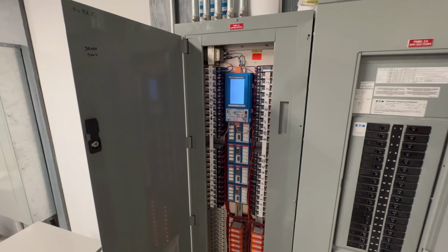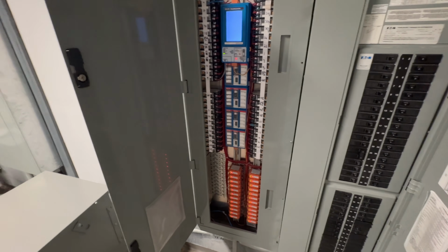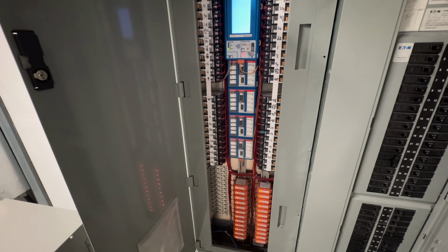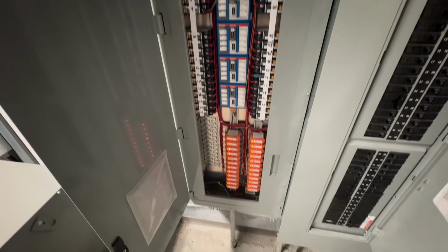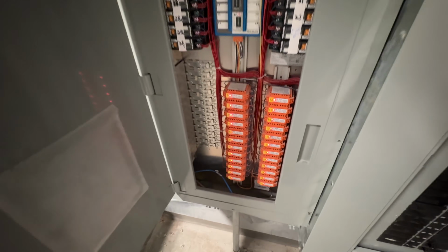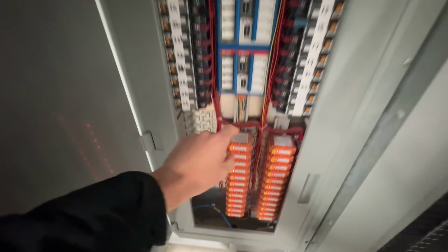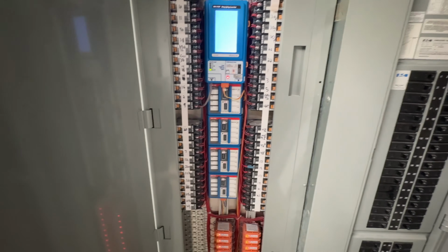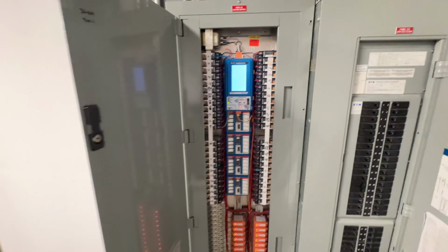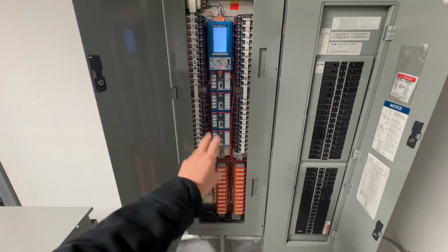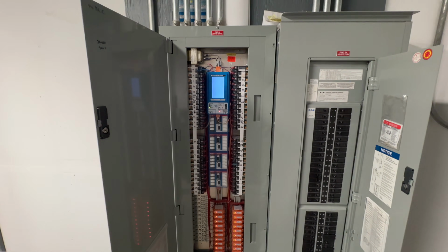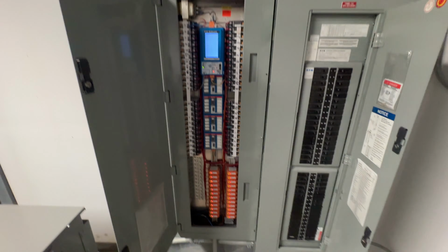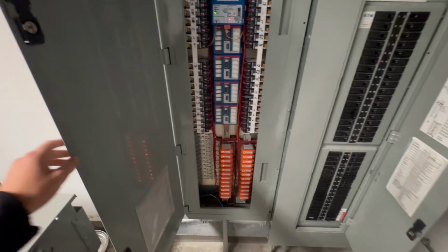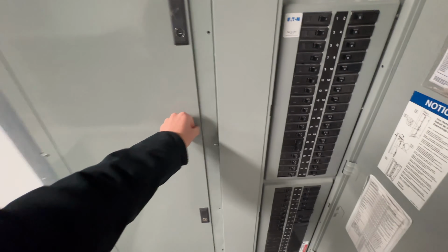Because most of the major lighting in this school is on lighting control, it needs to have the generator power going through this lighting control panel, because all these modules will turn on the emergency lights. So should the power go out and the lights are off, those will automatically turn them on and override any human input into the system, basically forcing every light that is a designated emergency light to come on.